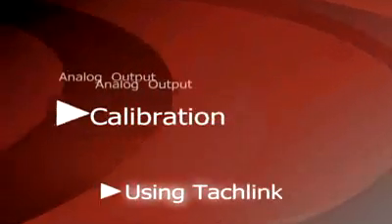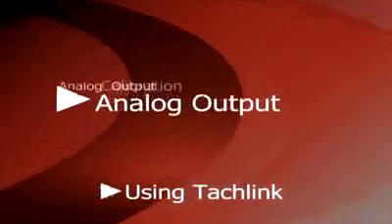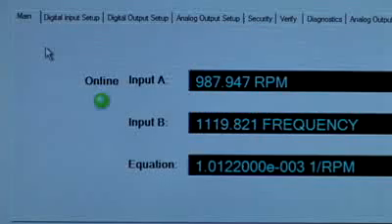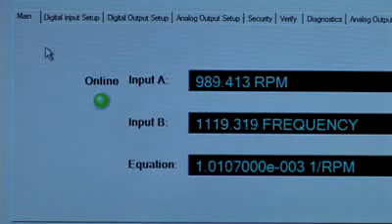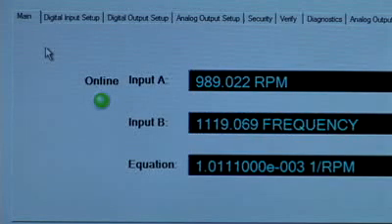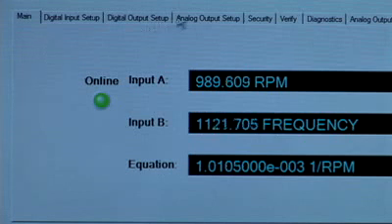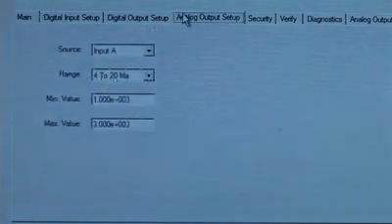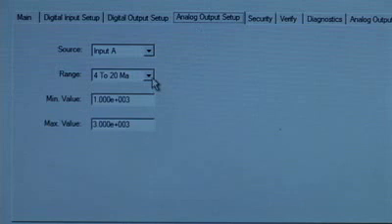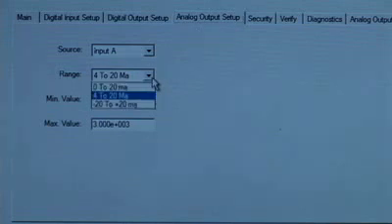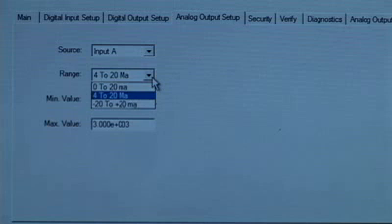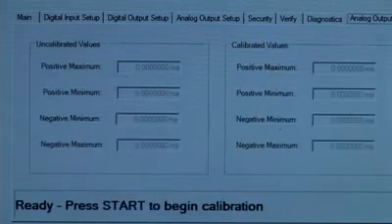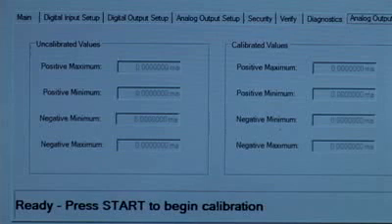Analog Output drives a precisely regulated current through devices such as recorders, meters, controllers and other instruments operated by a current loop. Analog Output is user-selectable in three ranges: 0 to 20 milliamps, 4 to 20 milliamps, and negative 20 to plus 20 milliamps. Each tachometer instrument comes calibrated from the factory.